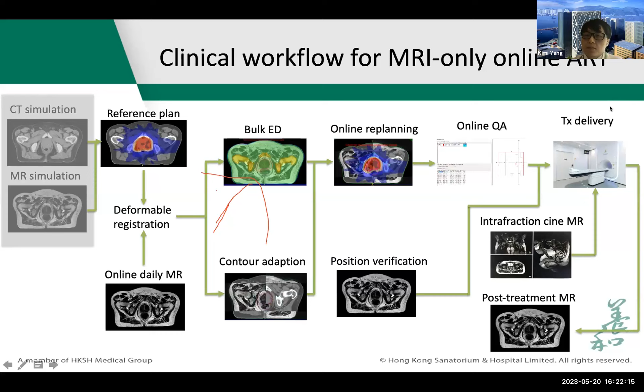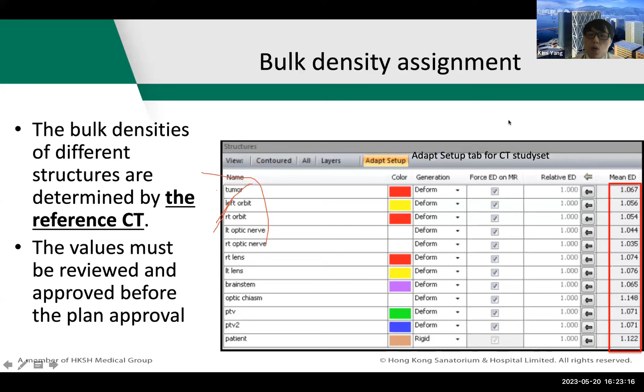And here is an example to show how we perform the bulk density assignment. So the bulk density of the different structures is determined by the reference CT. Here, this tab is called the Adapt Setup in Monaco. And you will notice that there's a mean electron density here; these values are read from the reference CT. And during the planning, you need to confirm if the values read here will be transferred and used in the online ART. If yes, you will click this arrow here to transfer the mean electron density read from the CT to the future daily MR images. And this part is mandatory. And before you approve the plan, you have to review the electron density values.